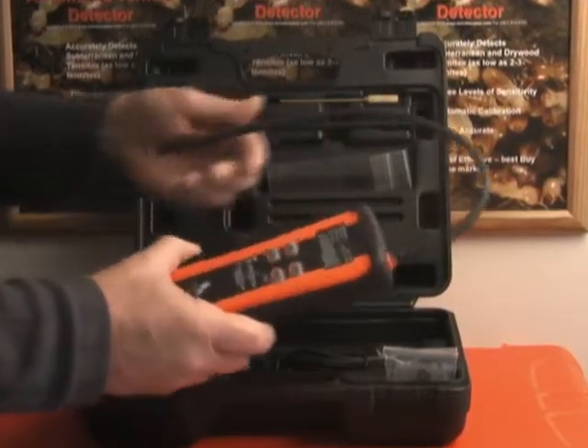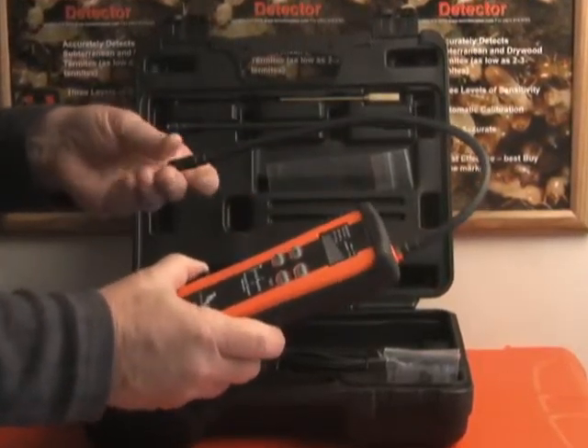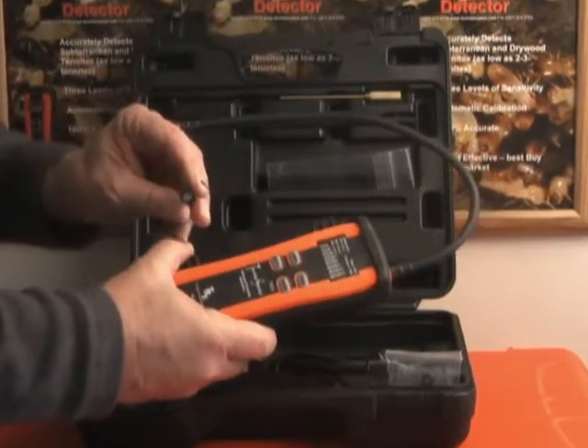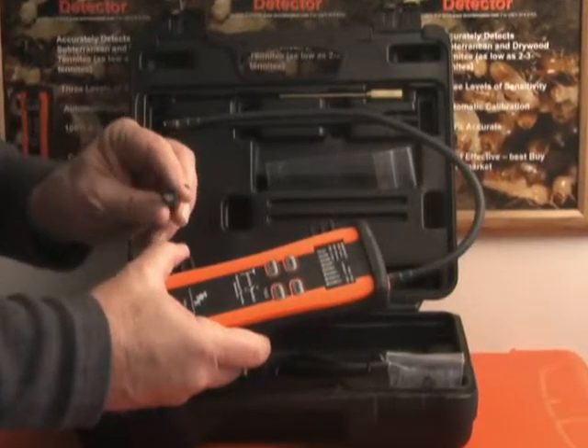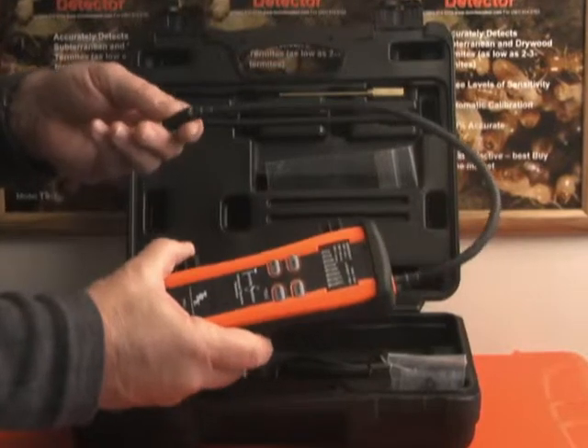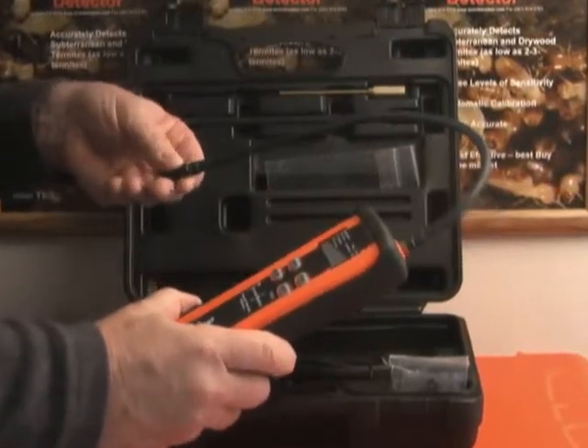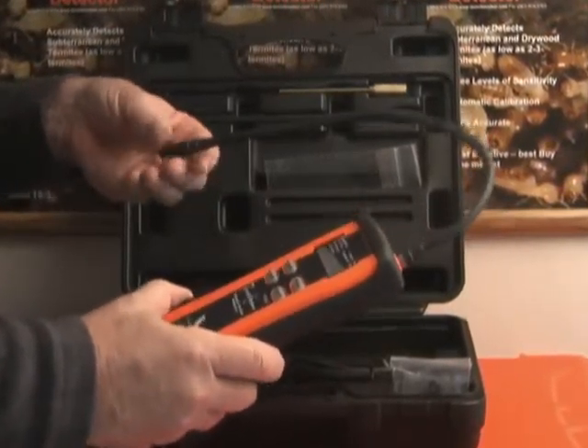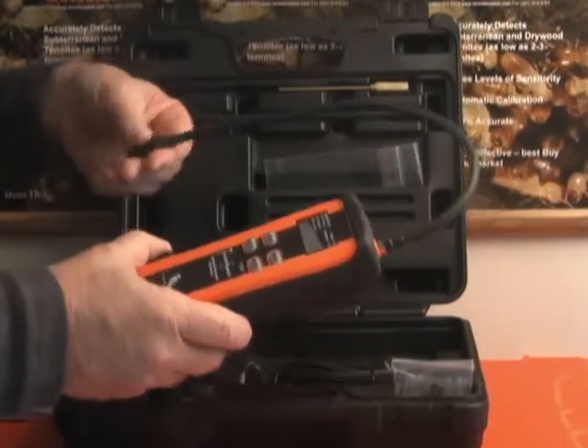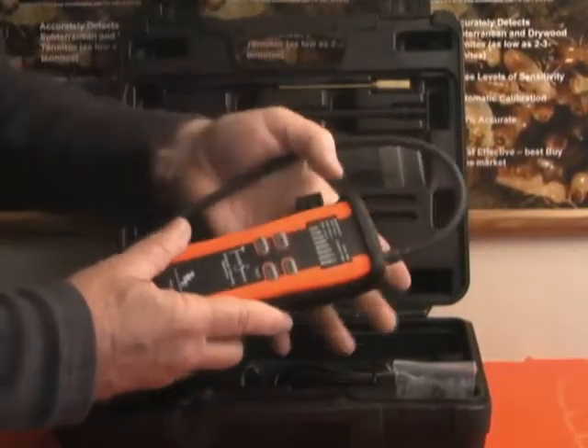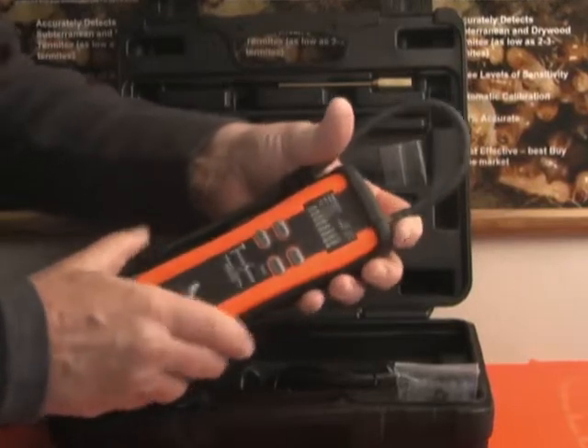On the tip of the wand, there's the nozzle, which contains a dust-water porous filter. It's replaceable. This filter, if it encounters water, will actually shut the unit down from taking in any samples to protect itself. Never operate this without one of these porous filters in it.